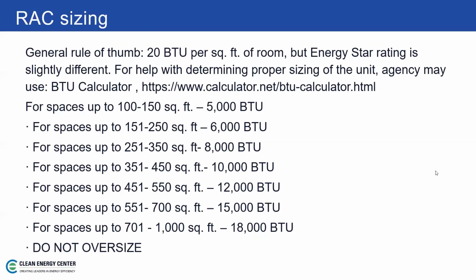As far as sizing for room air conditioners, pretty much everybody just goes by a rule of thumb, so about 20 BTUs per square foot of room area. Energy Star rating might be slightly different. There are different places out there on the internet where you can go for help, but the 20 BTUs per square foot probably should work for most applications.